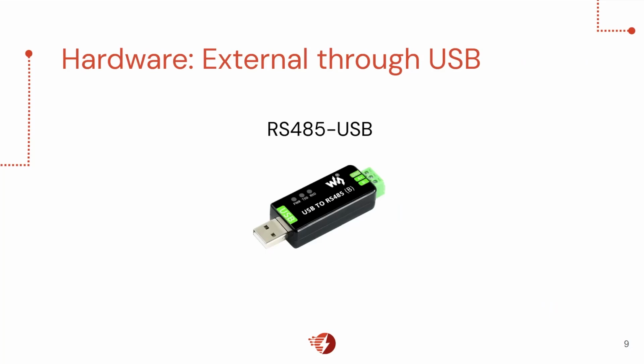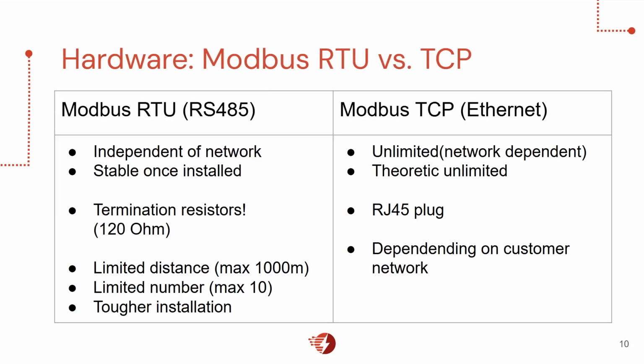Now we have another add-on for the controller. This is an RS485 to USB connector. This allows the user to have multiple RS485 connections on one controller. It is possible to daisy chain multiple RS485 connections to one single controller, but if one would like to have more RS485 connections, then this is an option for you. I've talked about Modbus RTU and Modbus TCP once or twice now, so I'll give you a brief introduction to the differences between the two, and the advantages and disadvantages. Modbus RTU is the physical connection that's made between the box and your asset.